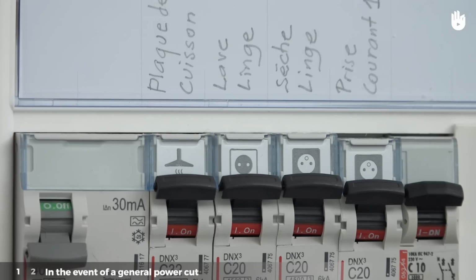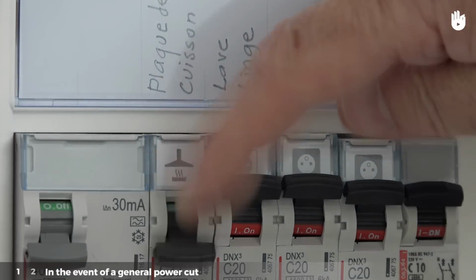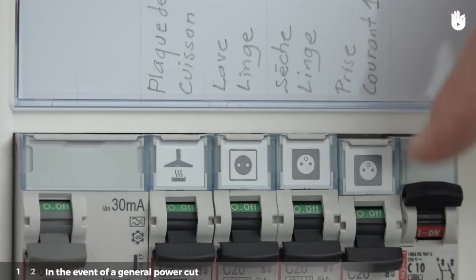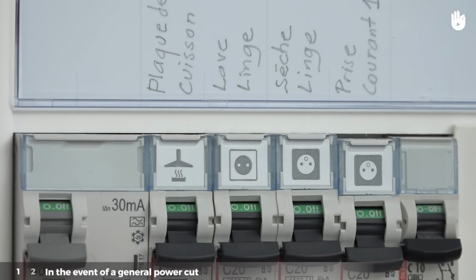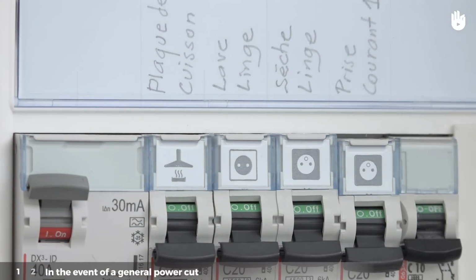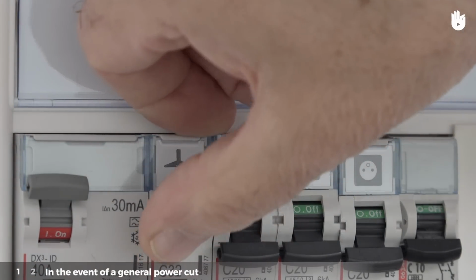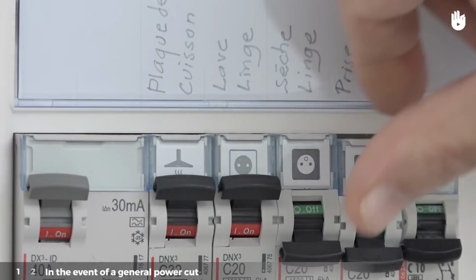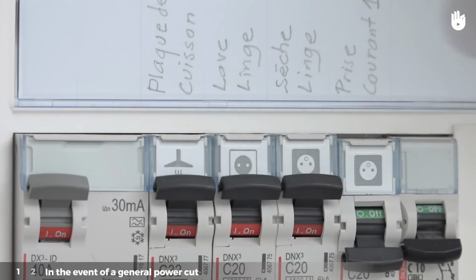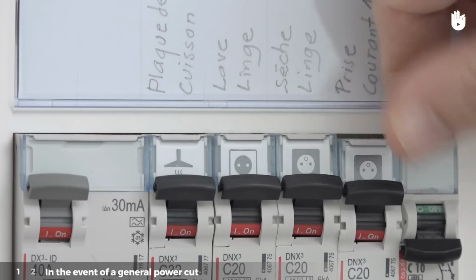Turn all the circuit breakers to the off position after the residual current protection system is triggered. Also keep the residual current protection system open. Then turn the residual current protection system back on. Then turn back on, one after the other, each of the protection systems that has been triggered. The protection which, when it is put in the up position, causes the residual current system to be triggered simultaneously, will indicate the faulty circuit.